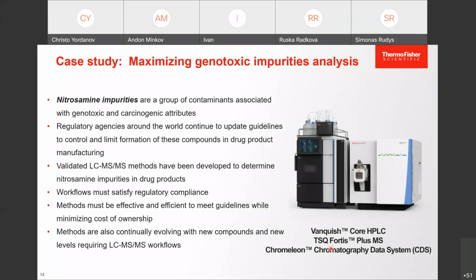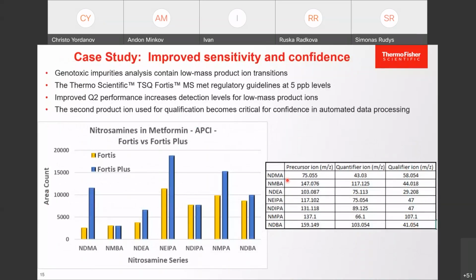So the method needs to run on Chromeleon software as compliance software, from data acquisition to data processing. I took this example on the Vanquish Core again, as a cost-effective solution. We have the entry-level Vanquish Core, the entry-level TSQ Fortis Plus, and Chromeleon as a solution for nitrosamine analysis. When we look at how small nitrosamines can be, the precursors for these seven nitrosamines are roughly around 100 m/z, and our qualifier and quantifier ions are most of the time around 50 m/z, even below that, which means our new collision cell can bring more performance to this method.